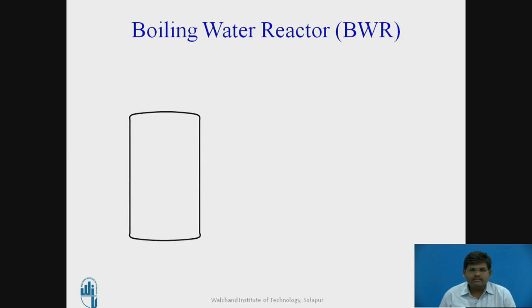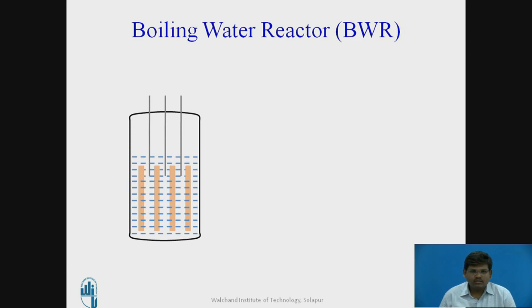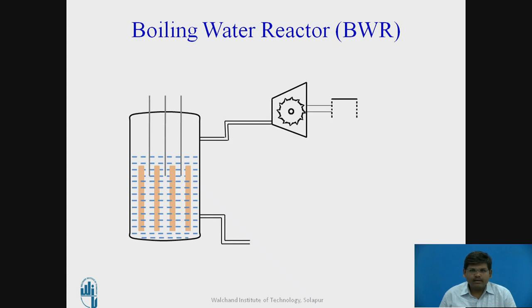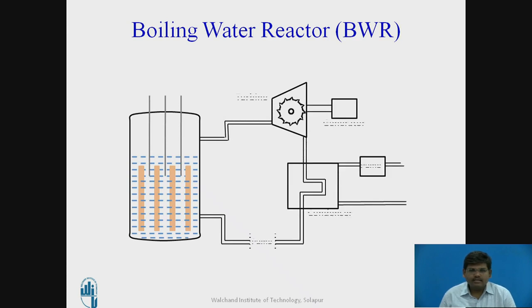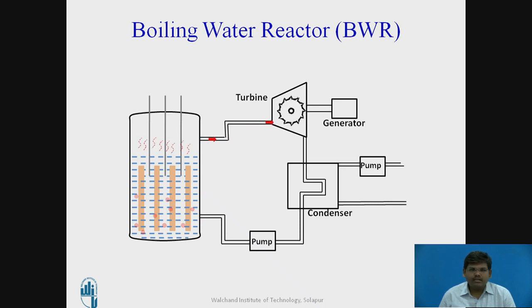Let us see the elements of the boiling water reactor. This is the reactor core, fuel elements, control rods filled with water, turbine, generator, condenser and cooling system. When a neutron is bombarded on the Uranium fuel, the chain reaction starts and because of this, a large amount of energy is released. Because of this energy, the water surrounding the Uranium fuel starts getting heated and steam is generated. This steam is allowed to pass over the turbine, which rotates the turbine at the desired RPM. This turbine in turn rotates the generator, generating electricity.